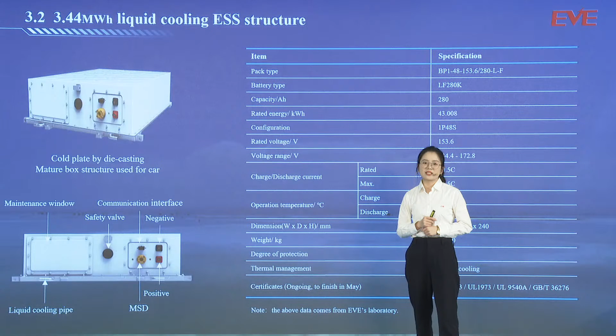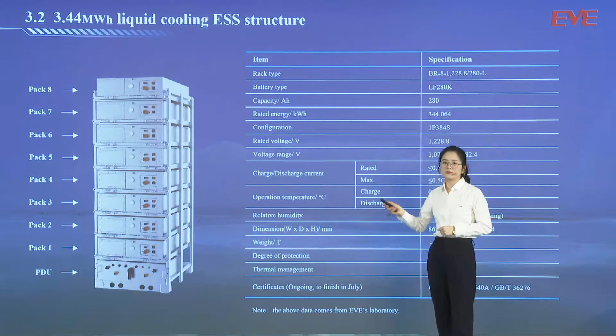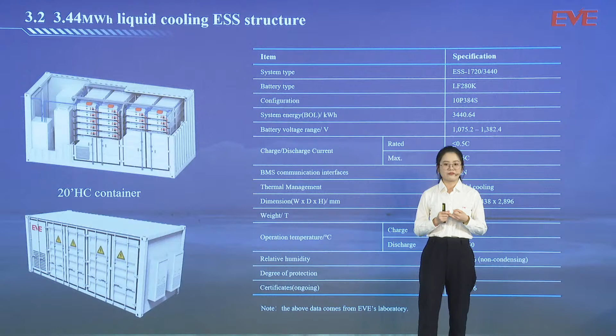Then we stack 8 battery packs in series into a 280 ampere-hour, 1228.8 volt rack as shown here, together with the PDU. 10 racks will be installed in parallel in the container. A standard liquid cooling 20-foot high container can store up to 3.44 megawatt-hour of battery capacity, which doubles the capacity compared with the air cooling solution with the same cell. At the same time, it also has low cost, good heat dissipation effect, and small temperature rise difference.